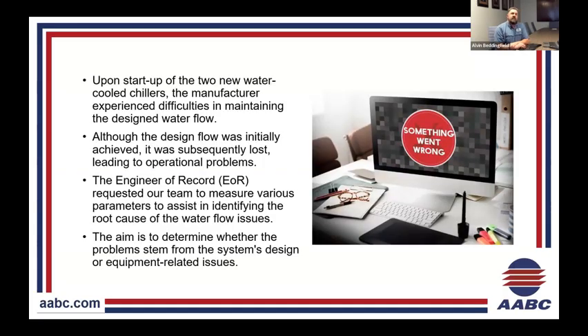So basically, jumping into it, we were contacted by an engineer at one of the campuses. The chiller manufacturer was out there and they kept having flow issues. The mechanical contractor went out there to assist. Both of them were having the same similar problems. Chillers would get started up, there'd be established flow, and then shortly after, flow would just completely drop off, and they couldn't start the chiller. So they spent about an 8-hour day trying to troubleshoot why the chiller won't start up, why it keeps losing flow.